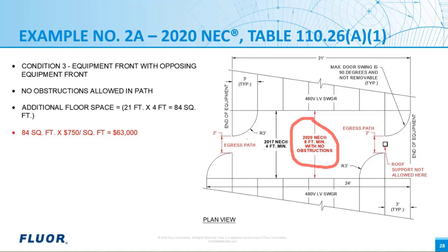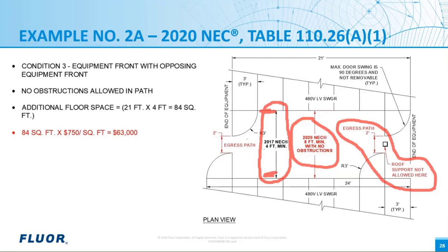All right, in this example, we see a condition 3 with the front of two equipment facing each other. There happens to be a 6-inch square permanent roof support in the entrance and egress path, which is centered perfectly between the two pieces of equipment. This will not work now, but it may have worked before. Now take a look at the black text here. In the 2017 NEC, a condition 3 required a minimum of 4 feet spacing between these equipment, with no consideration given to whether the doors of the equipment are open. Now take a look at this red text that's circled. Now we're going to need a minimum of 8 feet front to front in a case like this, with no obstructions in that 24-inch path.